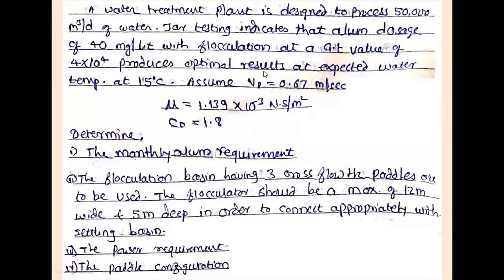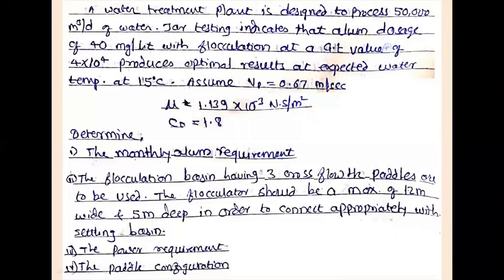Let us solve the problem based upon the design of a Carey flocculator. A water treatment plant is designed to process 50,000 cubic meters per day of water. Jar testing indicates that an alum dosage of 40 mg per liter with flocculation at a GT value of 4 × 10⁴ produces optimal results at an expected water temperature of 15°C. Assume Vp is equal to 0.67 meters per second.